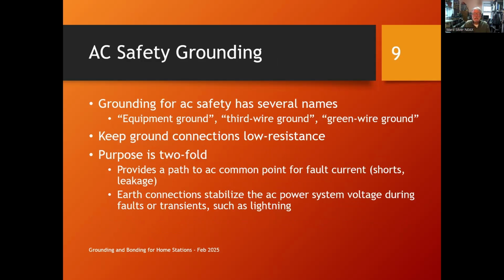Let's talk about AC safety grounding for a minute. Grounding for AC safety, depending on how old your electrician is and where you are in the country, could have any one of several common names. The current common name that's used in all the standards is equipment ground. When you talk about equipment ground, that's a connection from your equipment to the central AC service grounding point. It can also be called third wire ground because that's the third wire in the power plug. It can also be called green wire ground because these wires are often green. That's the standard for insulation to indicate that you have a ground connection here.